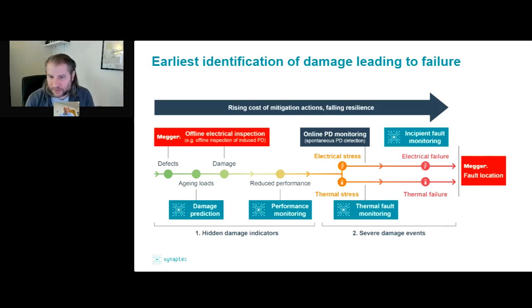In terms of electrical stress, we could see incipient faults, an actual but temporary breakdown indicating something wrong with the insulation at that location. On the thermal side, we could see hotspots start to emerge. As highlighted earlier, that lets the operator intervene early before something blows up and becomes an outage, so the asset can be looked after until a repair is possible.